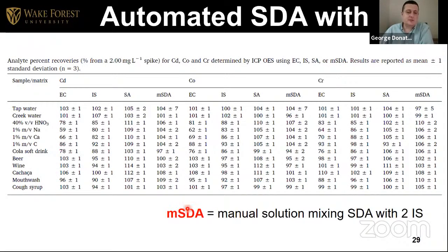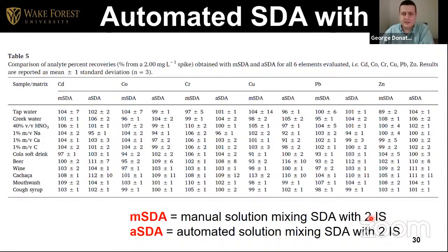We applied that first doing the manual SDA with two internal standards just to check whether the two internal standards method works. And you can see the recoveries are very similar to the standard additions. Here we have manual SDA against the external standard calibration and internal standard additions for 3 different elements, and the recoveries are quite good. Then we compare the manual SDA with automatic. In both cases, we have 2 internal standards, and there is not much of a difference. So we're happy to see that it's possible to do manual or automatic, and there is no change in the accuracy of the measurements. And again, we applied it to some nasty solutions. You can see here, for example, calcium is a very nasty concomitant that can mess up the measurement, and some others here that we just diluted, with no digestion, and the recoveries were quite good.